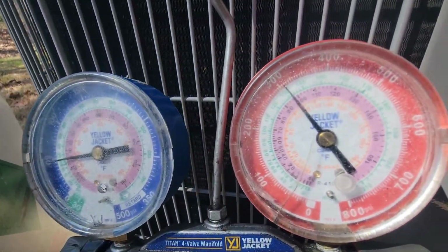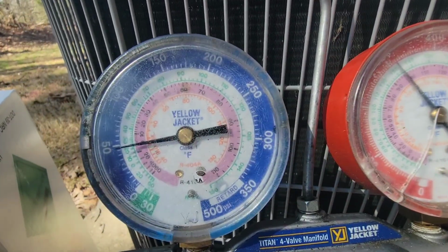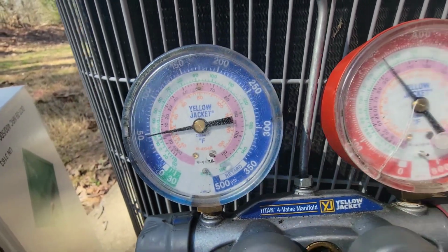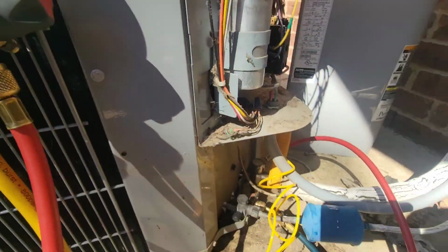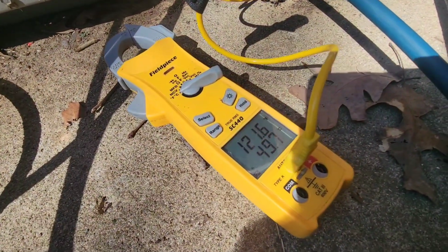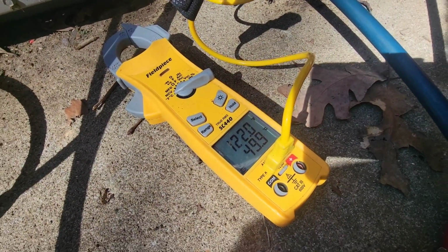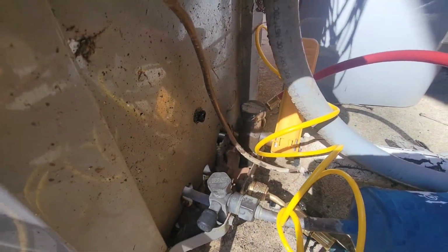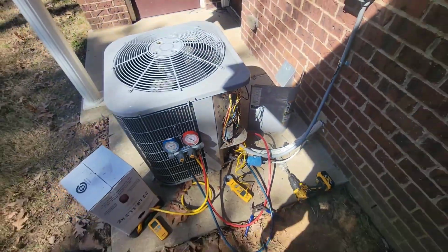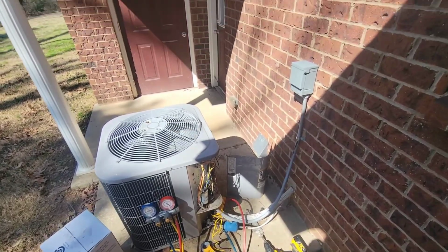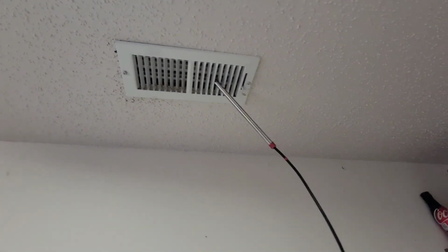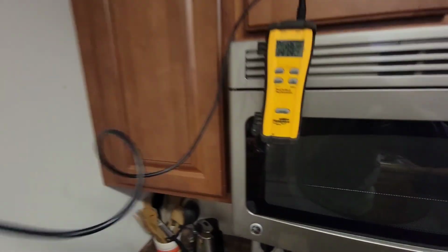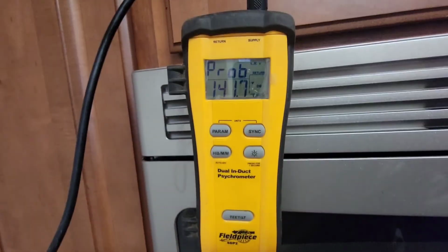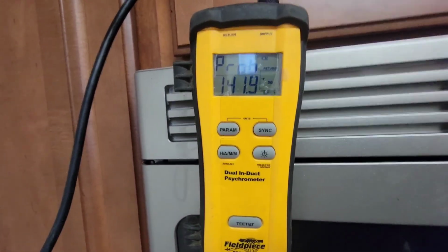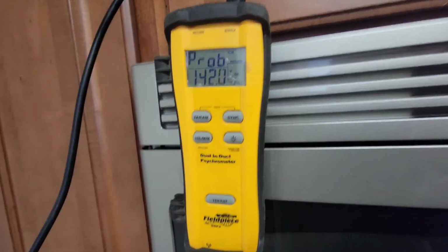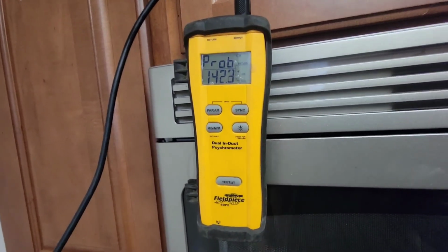Okay, awesome. 121 degrees on that vapor line. Let's go inside and check the temperature split. Got the probe inside the supply vent, and this is a dual In-Duct psychrometer. It says it's 141 degrees, and I know that's not just the heat pump. We have those heaters, the heat strips are running as well.